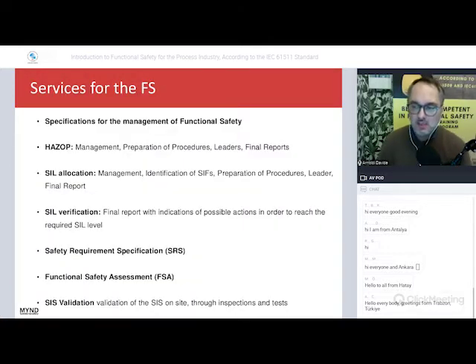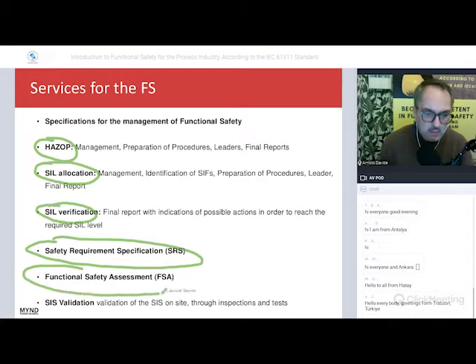The service for functional safety that we can provide by my company, you can see that is everything included in the standard 61511. So we will speak during this webinar about HAZOP, and I suppose the HAZOP is common for all of you. HAZOP is the risk evaluation of hazard for the project. SIL allocation is an additional step for functional safety, including SIL verification, safety requirement specification, and this is very important for companies right now, that is demonstration of compliance with the 61511 standard.